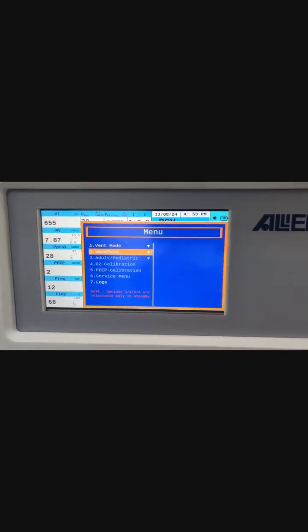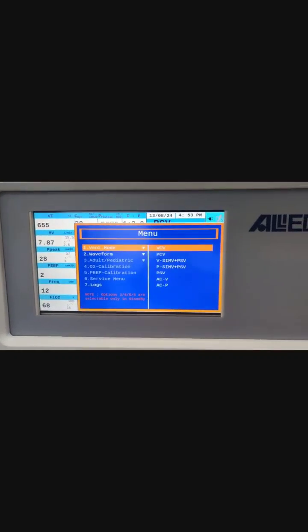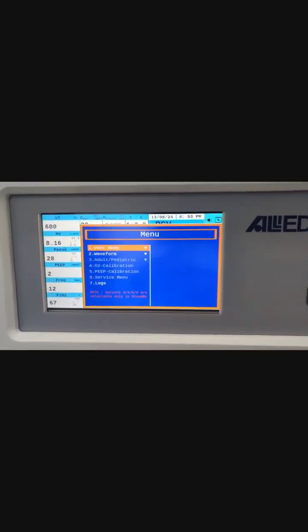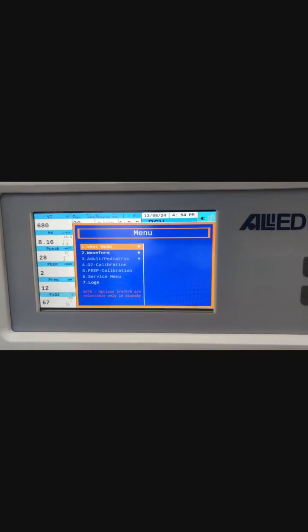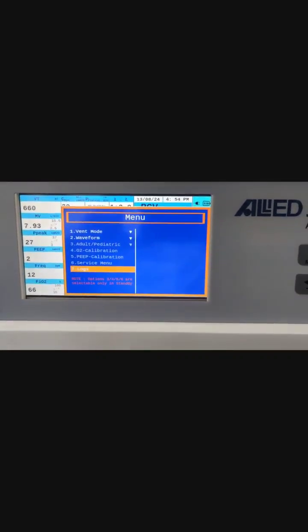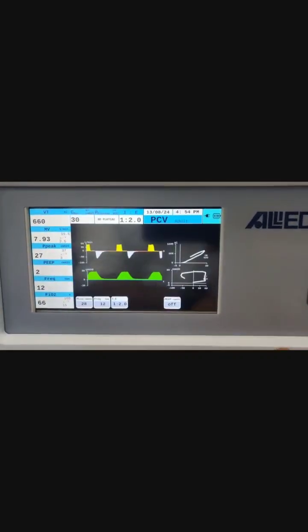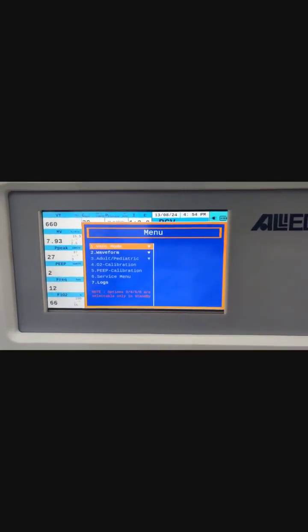When the machine is running, you will be able to select only 3 options. One is the ventilator mode, the second is the waveform, and the third is the logs. The rest of the options are deactivated. To select those options which are deactivated, you first have to move it to the standby mode.